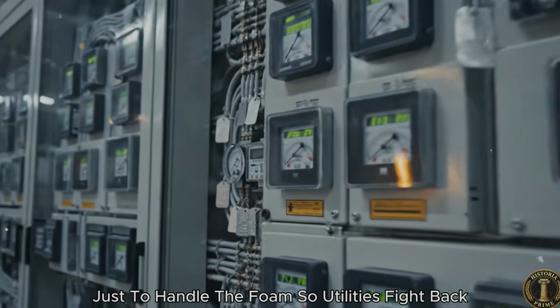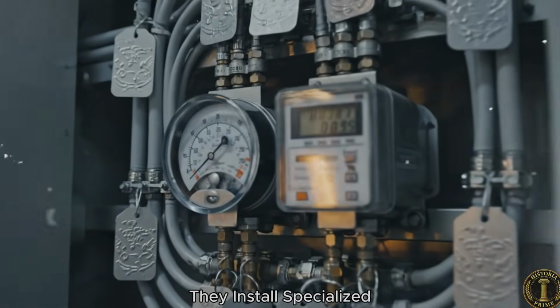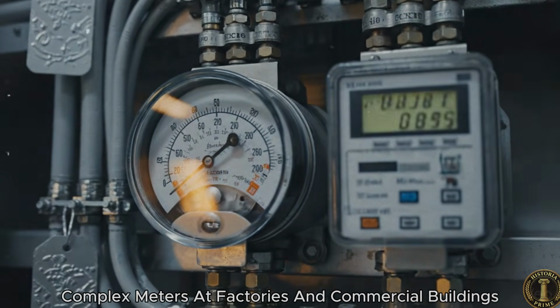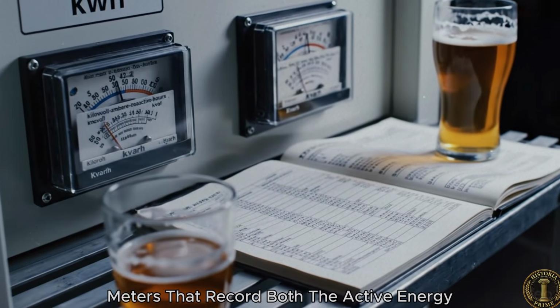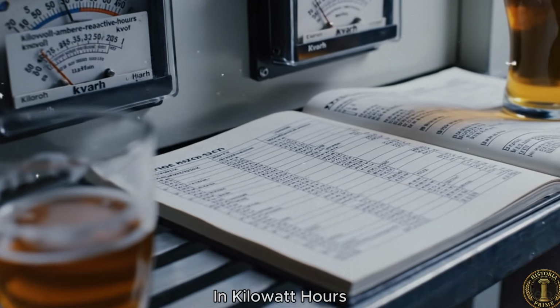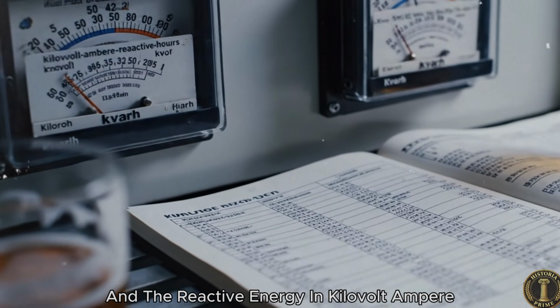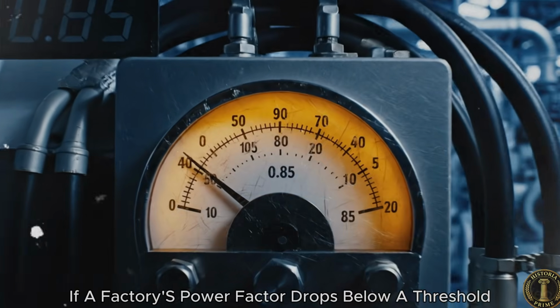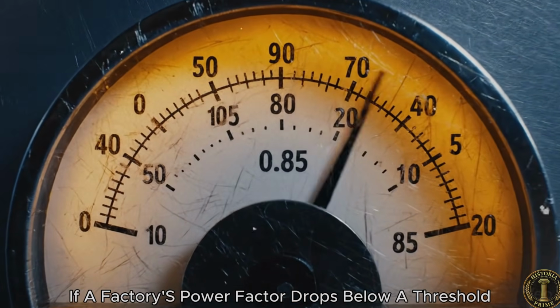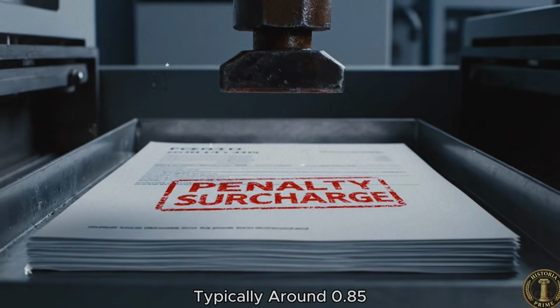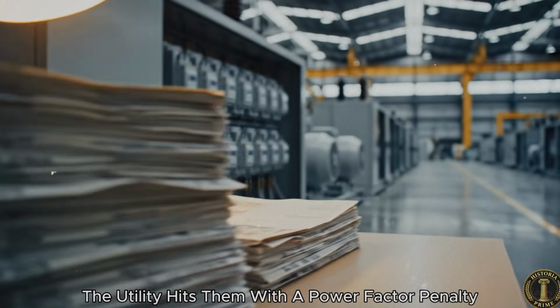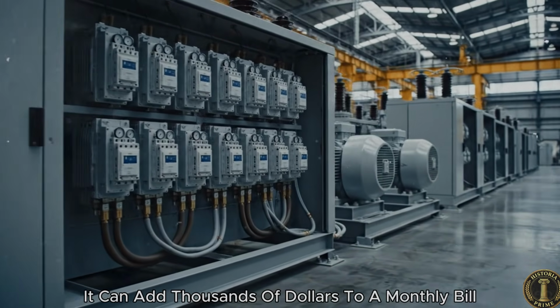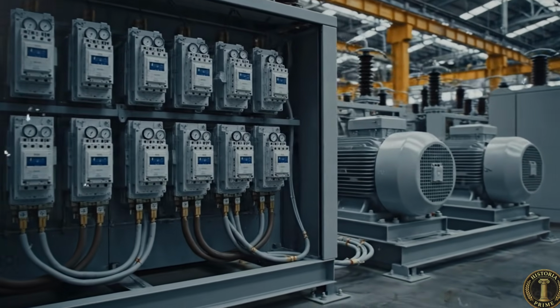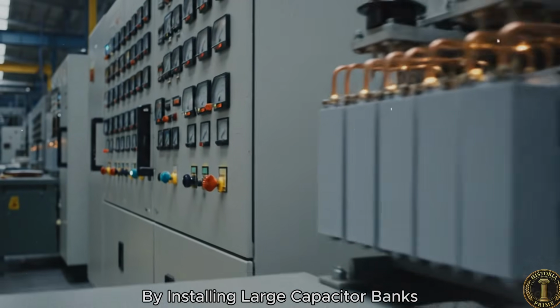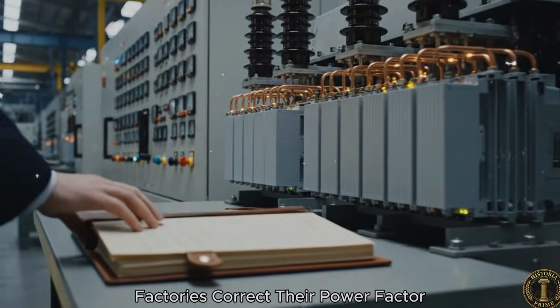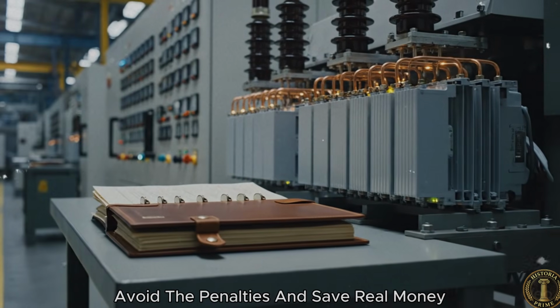So utilities fight back. They install specialized, complex meters at factories and commercial buildings. Meters that record both the active energy in kilowatt hours and the reactive energy in kilovolt-ampere reactive hours. If a factory's power factor drops below a threshold, typically around 0.85, the utility hits them with a power factor penalty surcharge. It can add thousands of dollars to a monthly bill. By installing large capacitor banks, factories correct their power factor, avoid the penalties, and save real money.